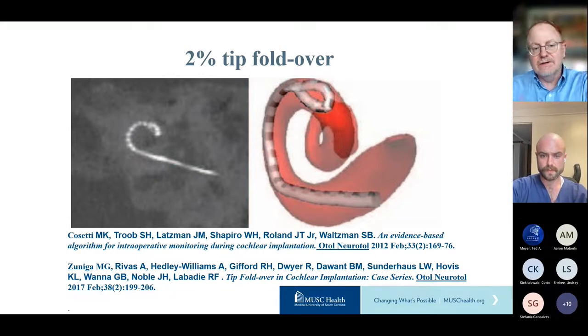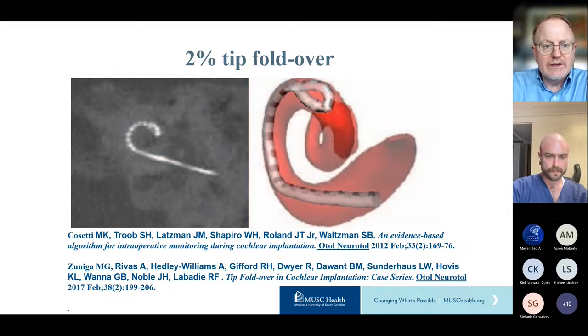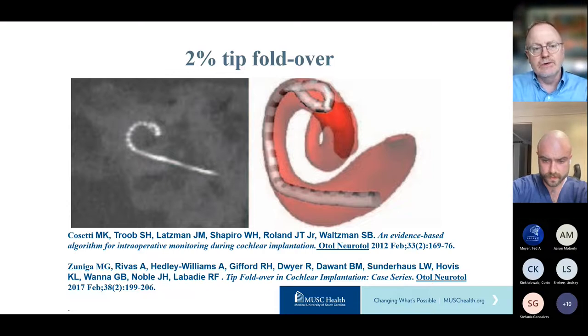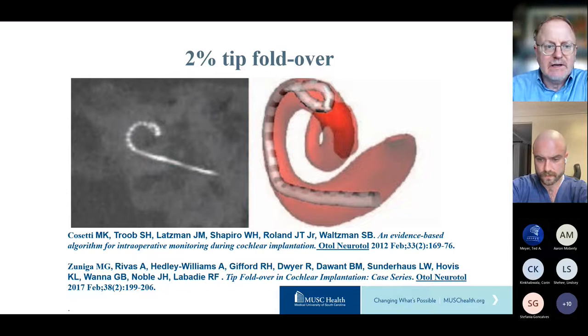It's very difficult to detect without an intraoperative CT scanner. You can use flat plates or fluoroscopy, and if you align it correctly, that will help you detect this. Spread of excitation, which is becoming more standard on cochlear implant testing portals, will also help alert you that this may be happening.